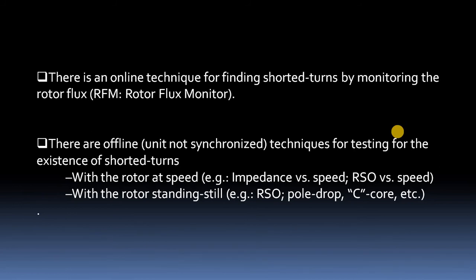The offline technique means we are not synchronizing the unit to the grid — not generating any active or reactive power. Offline techniques for testing the existence of shorted turns, with the rotor at rated speed, include plotting a graph of impedance versus speed or RSO versus speed. When the rotor is at standstill, we can identify shorted turns using the pole drop test or the C-core test.